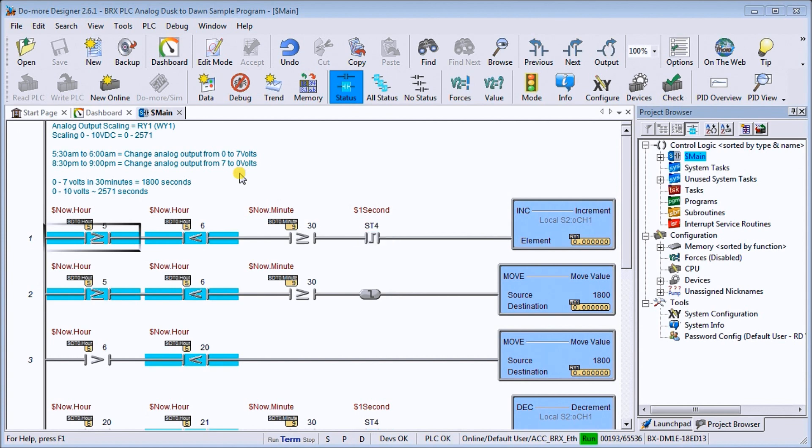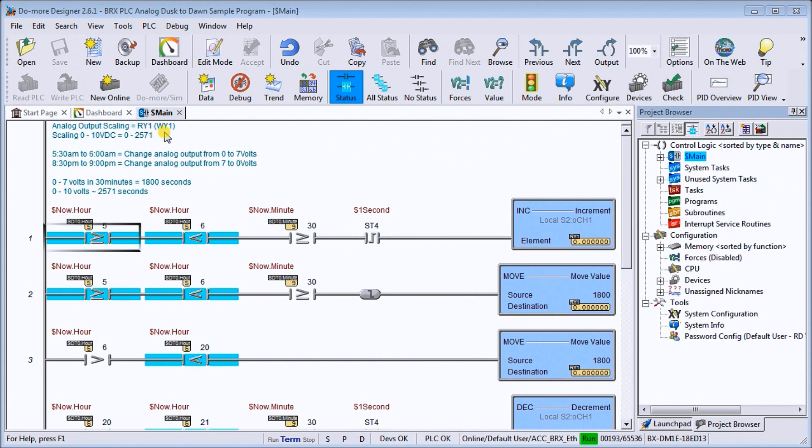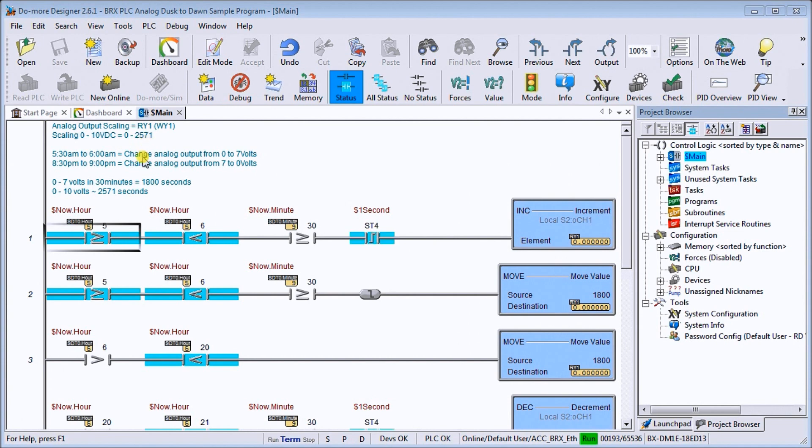Now if we look on the screen here, we can see that we have our analog scaling. It's RY1, which represents WY1, which is the output of our BRX PLC. And our scaling is from 0 to 10 volt DC, or the output will equal 0 to 2,571.